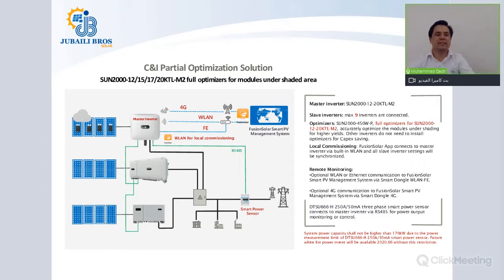Okay, I'm going ahead. So this is the first case where partial optimization is done using the SUN2000 12, 15, 17, 20 kilowatt -M2 version. You are doing full optimization. It means that all the solar PV modules connected to the master inverter, the 12 to 20 kilowatt size inverter, will have optimizers, and these solar PV modules will typically be under a shade due to cloud, nearby building, or a tree, while the rest of the inverters within this scenario will not have optimizers. This is the reason it is called partial optimization. It means part of your PV plant will have optimizers going to the 12 to 20 kilowatt size inverter. Since we have discussed the local commissioning and remote monitoring for this scenario, I will skip that part.